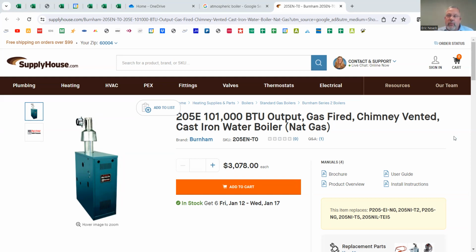One of the other rules of thumb with boilers is they definitely work best, and it's best practice, if all the radiators on the boiler are the same, meaning they're all the same style and the same size. When you have a mix of, say, cast iron baseboard and copper fin baseboard and maybe some old stand-up sectional style radiators, it can be challenging to balance out a home like that. They always work best when there's the same type and same size of radiators throughout the home.